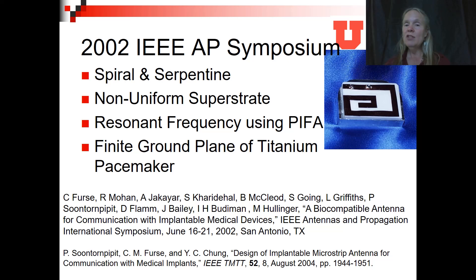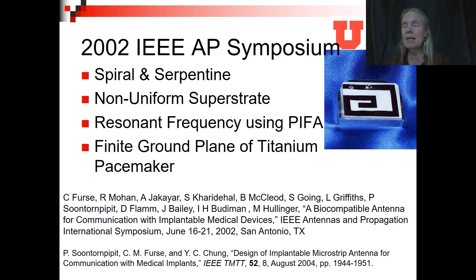In 2002, at the IEEE AP Symposium, we presented work on spiral and serpentine antennas. We used a non-uniform superstrate material, the resonant frequency of the PIFA, and the finite ground plane of the titanium pacemaker. We basically took a dipole antenna, split it in half by putting a ground pin on the left — making it into a PIFA — then rolled and coiled it up, either in an S or a serpentine shape, in order to make the antenna smaller. This produced a coiled or serpentine PIFA shape.